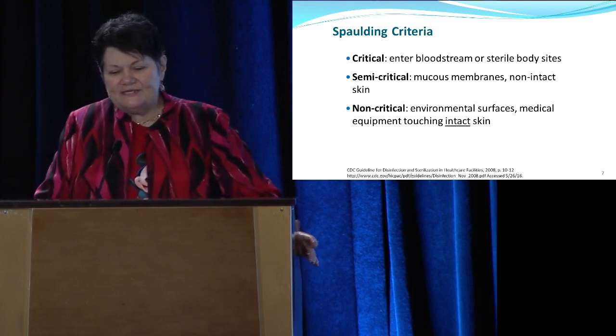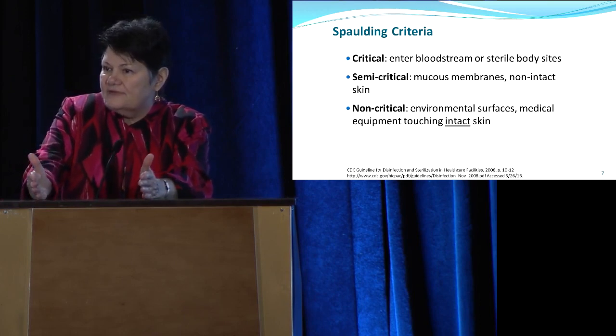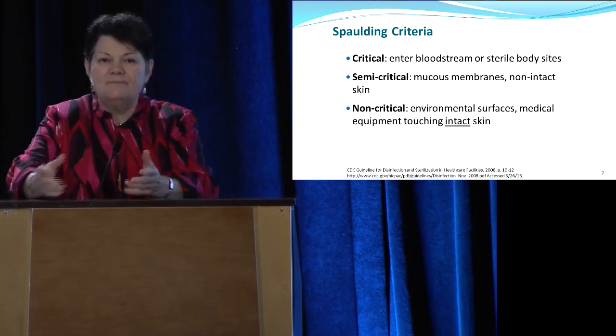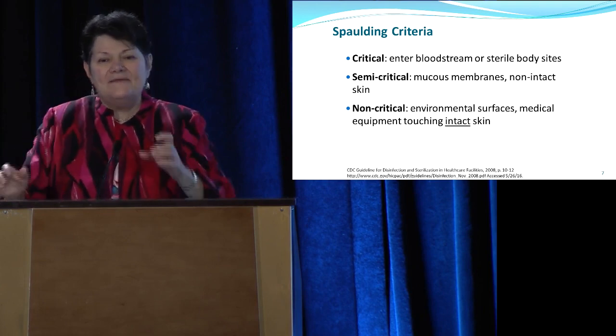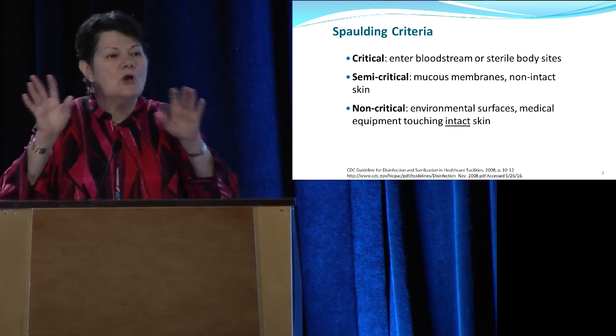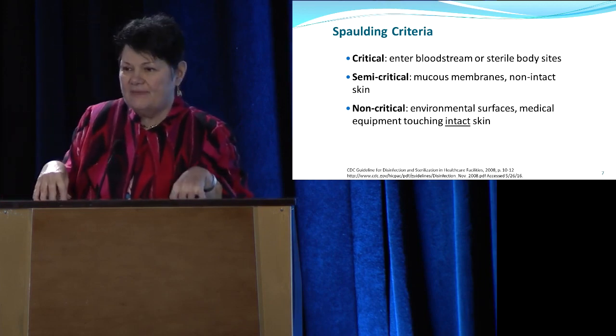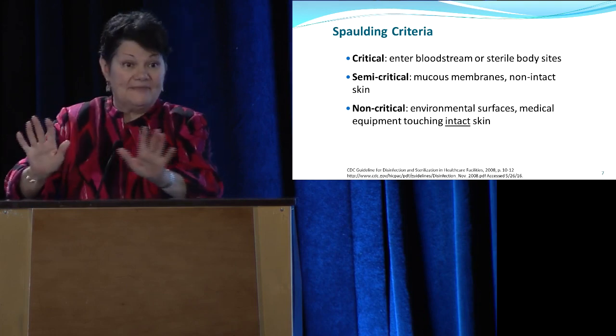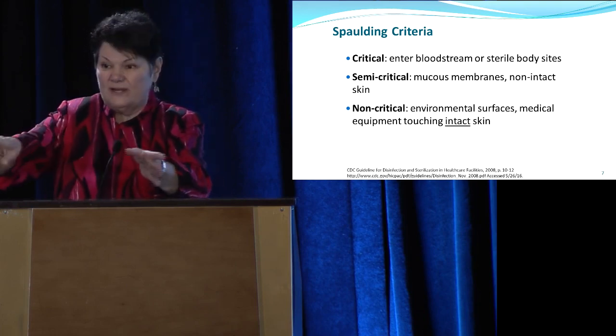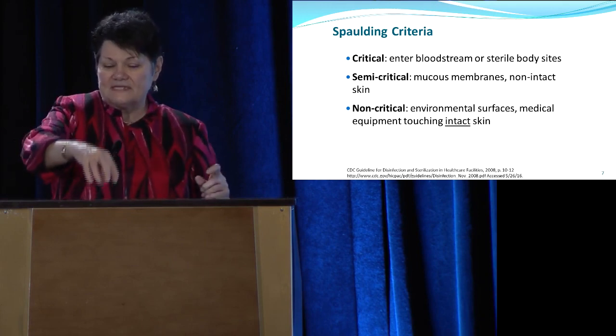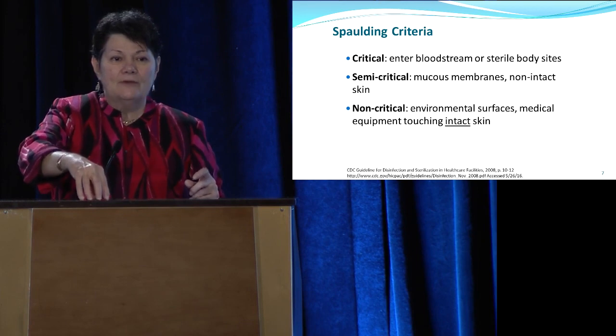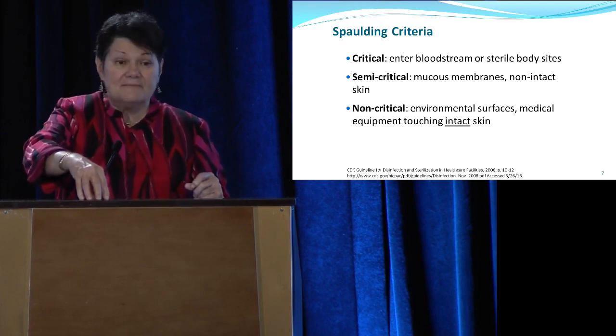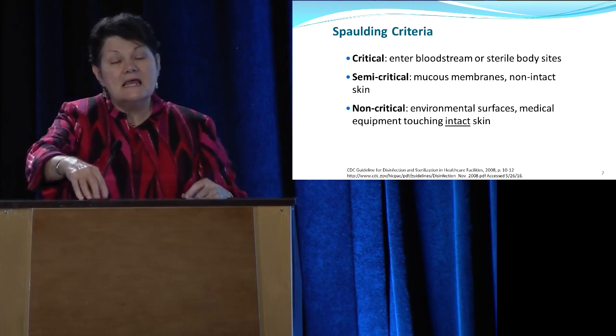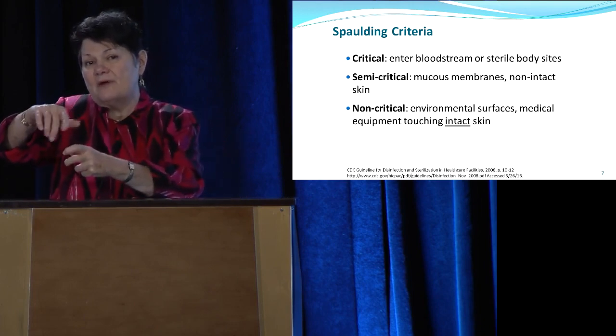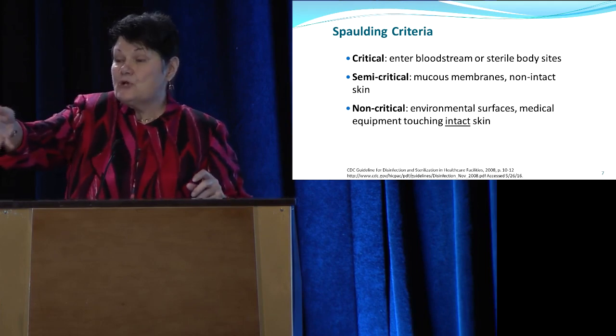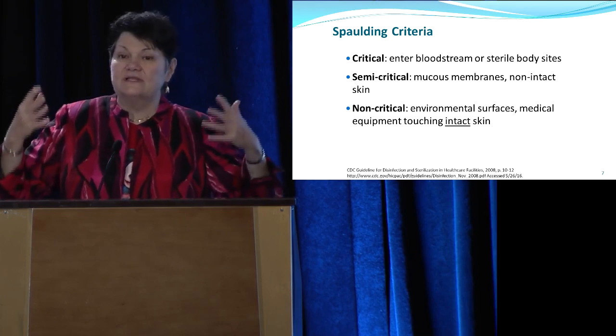One of the things that we see, you know those big containers of gel? It's like a 3-gallon plastic thing, and people refill their bottles from that, and then they put them in what I call an incubator. You call it a warmer. I call it an incubator. Often those are refilled by the sink because sometimes it glops over and you don't want to get it on the floor or the counter, so you do it over the sink. The top of the ultrasound bottle gets put down on the sink surface or next to the sink that's contaminated with water bugs, Pseudomonas, and everything else. And then it gets put on the top of the bottle, and then the bottle goes back in the incubator so that by the time it gets used, it is absolutely loaded with bacteria.